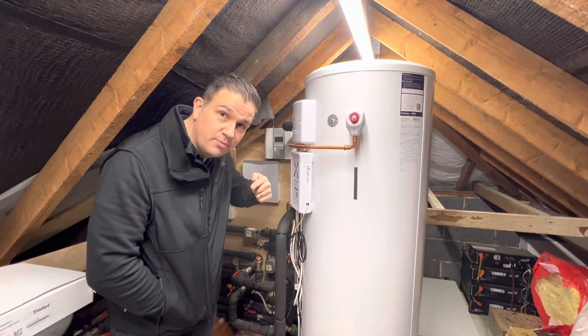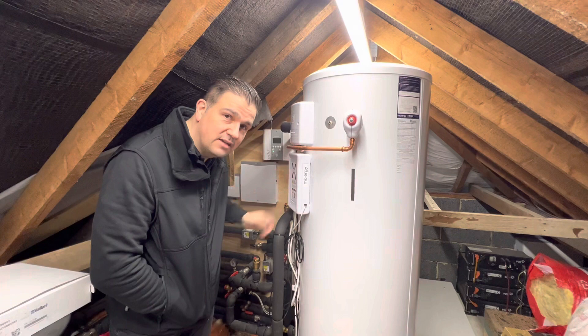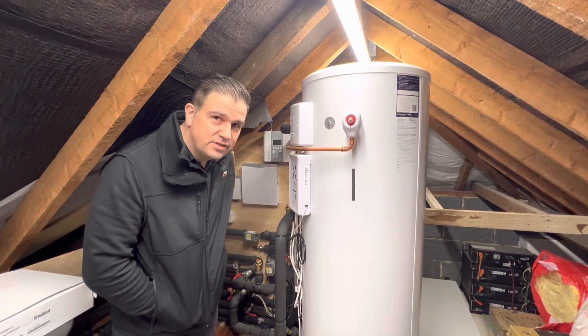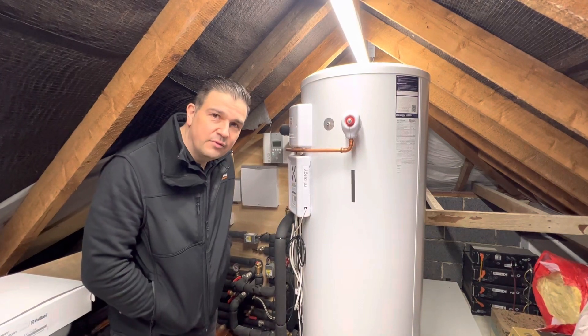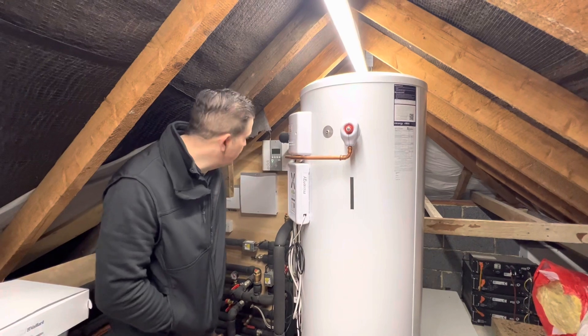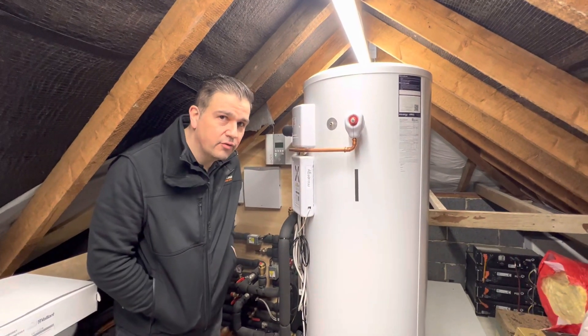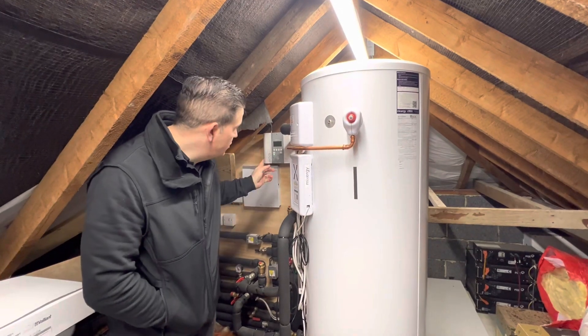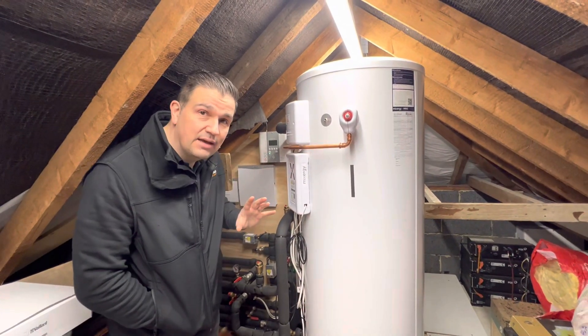The Eddi should have pulled that energy back in to feed the immersion heater, but it wasn't. It wasn't even really indicating anything was properly happening — it was only showing around 0.2 or 0.3 kWh coming back through on the Eddi, which obviously made us think there had to be an issue.